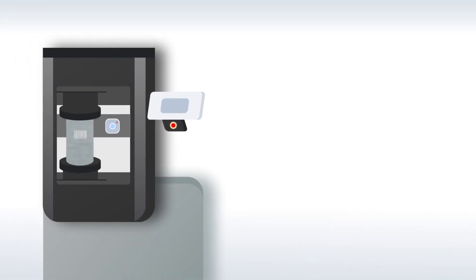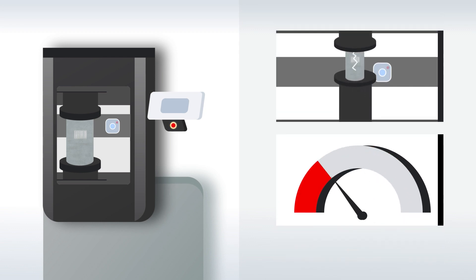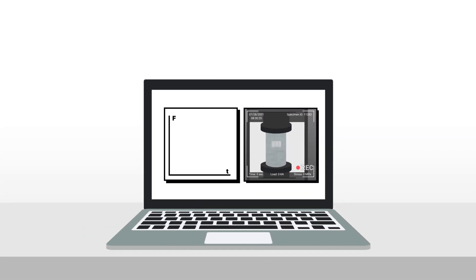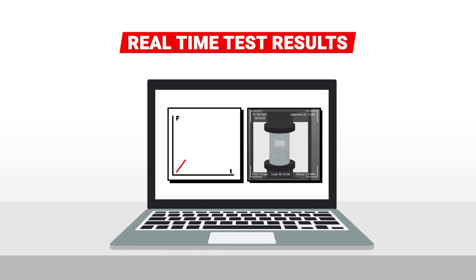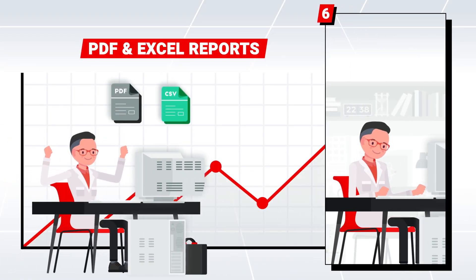The smart camera records the whole test in real time, which will be automatically performed at the correct load rate up to failure. The video recording not only proves test execution but also provides test results that cannot be altered, as the load and strength values are displayed in real time and watermarked at the end of the test.